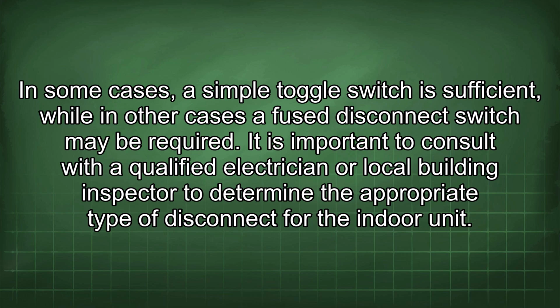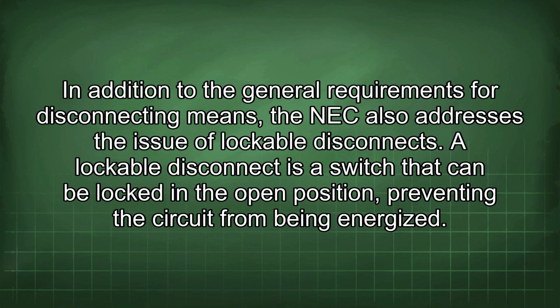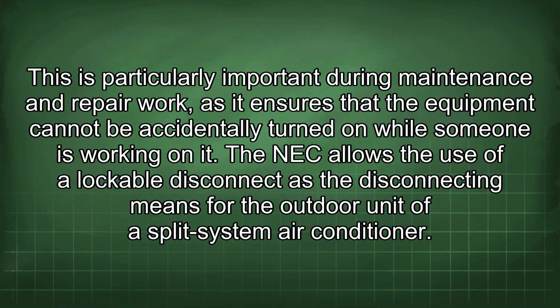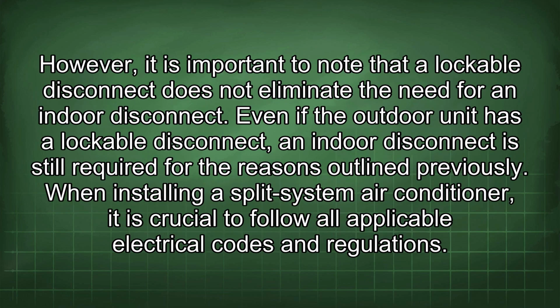for the indoor unit. In addition to the general requirements for disconnecting means, the NEC also addresses the issue of lockable disconnects. A lockable disconnect is a switch that can be locked in the open position, preventing the circuit from being energized. This is particularly important during maintenance and repair work, as it ensures that the equipment cannot be accidentally turned on while someone is working on it. The NEC allows the use of a lockable disconnect as the disconnecting means for the outdoor unit of a split-system air conditioner. However, it is important to note that a lockable disconnect does not eliminate the need for an indoor disconnect.